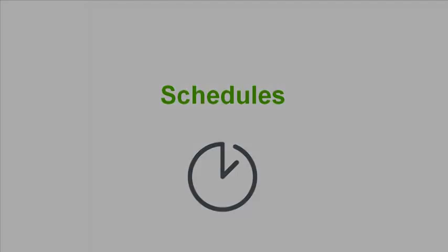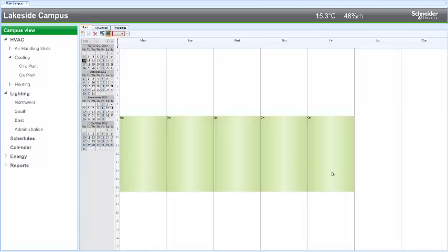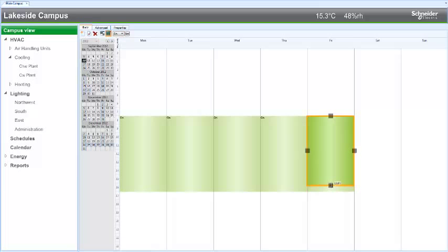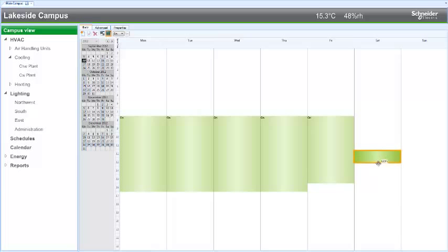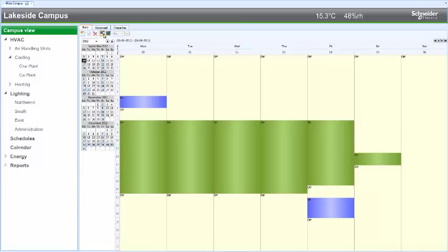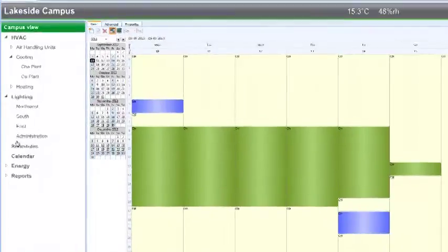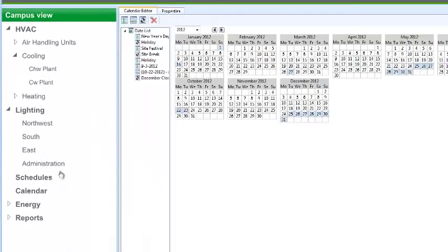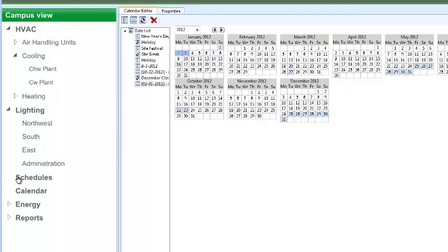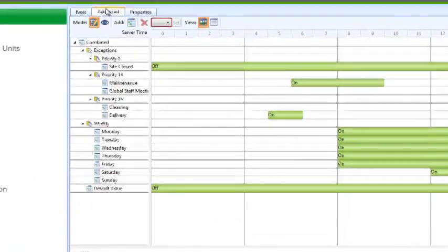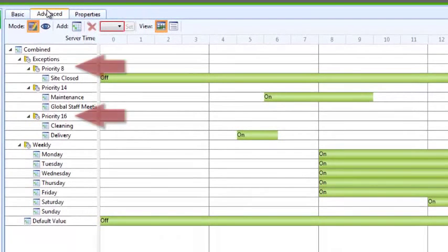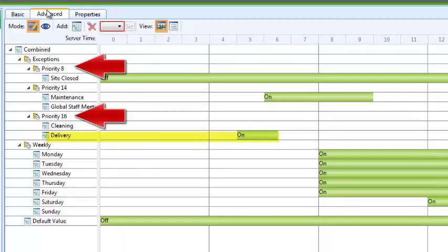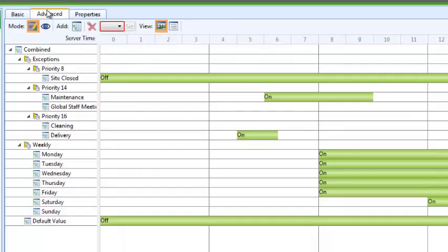Multiple buildings can be managed effectively through the use of schedules and calendars. Using a Microsoft Outlook-like recurrence calendar, it's simple to click and drag to create weekly events. Calendars are used so that special exceptions, such as holidays, can be created once and then reflected in all schedules across a facility. Events are assigned priorities so the system knows what to do if there are conflicts, such as a delivery scheduled on a holiday.